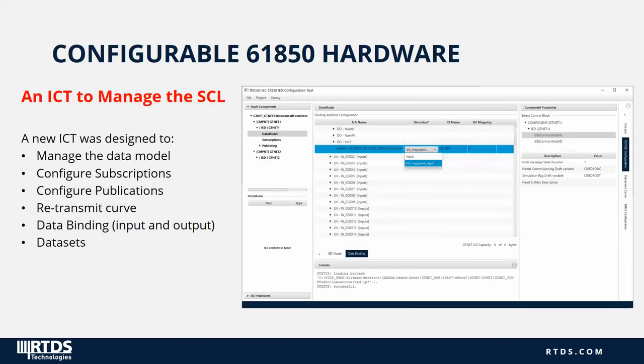An ICT is used to manage the SCL. The ICT was designed to manage the data model itself, configuration of subscriptions, configuration of publications, the retransmit curve, manage the data binding for input and output, and the dataset content.